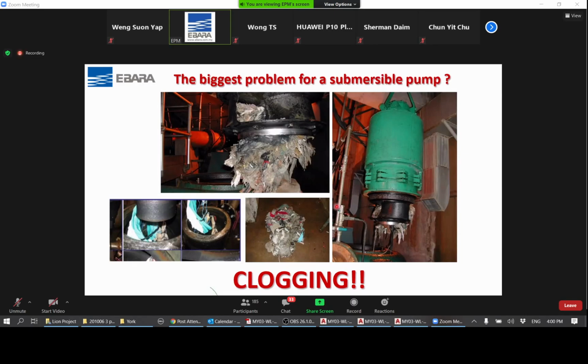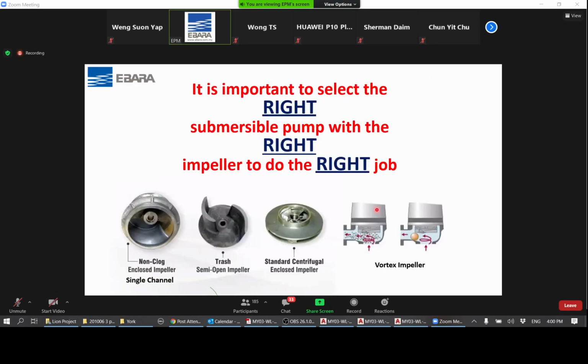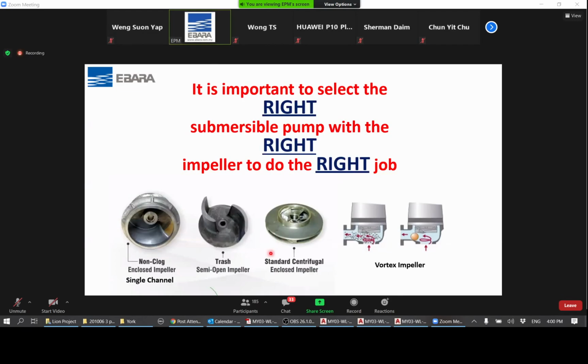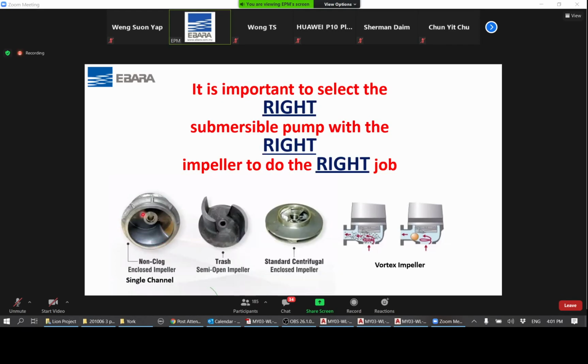impellers that are able to handle some form of solid particles. And you can see from here, compared to, let's say, a normal standard pump impeller, a clean water pump impeller, which has a very small channel, a submersible pump can have different impeller designs. For example, this is what we call a non-clog closed impeller, a single channel impeller. What it means is that the size of this impeller, or rather the vanes, are big enough to let solid particles go through without choking the impeller to a certain extent.